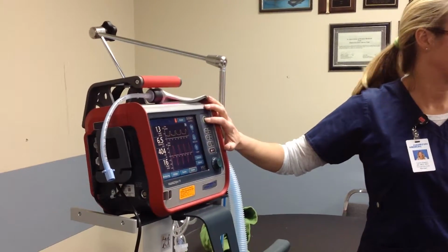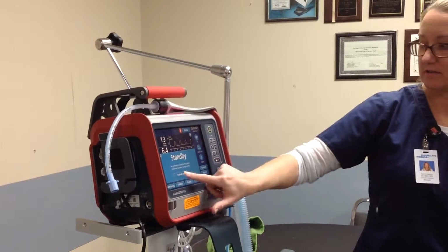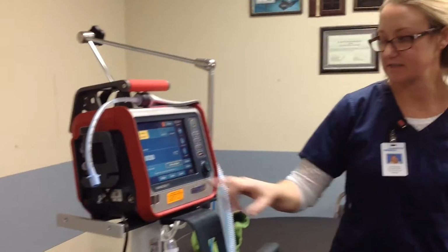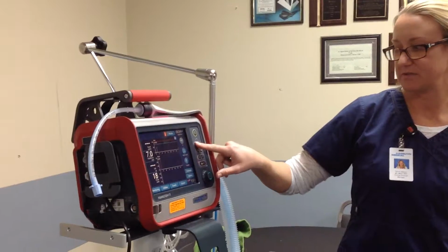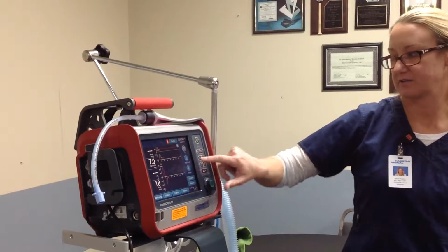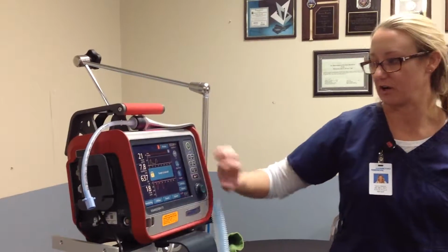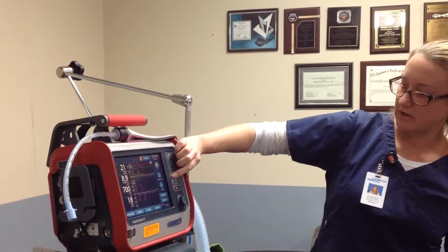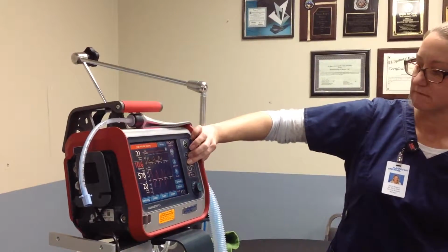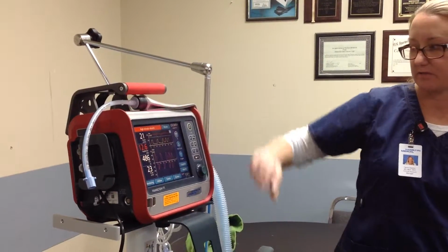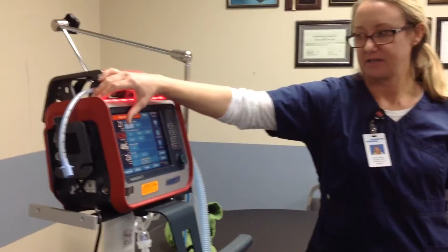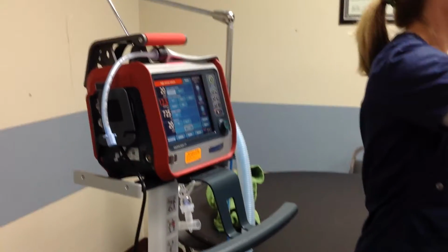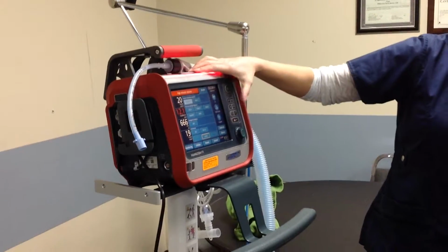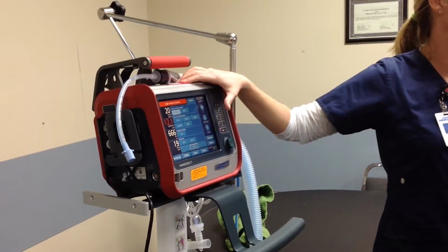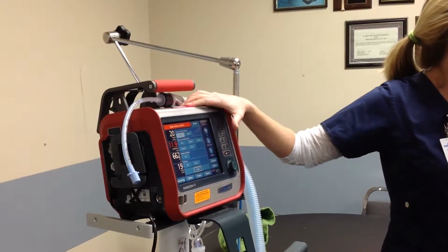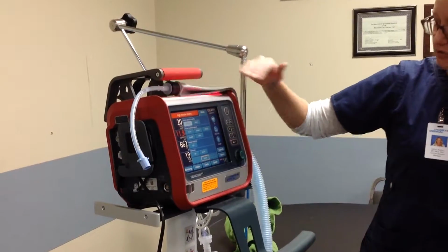This is also your start standby screen. So if I push this, it's a two-step process to activate standby. This dims the screen. This locks the screen so that you can't inadvertently make changes. This lung button gives you manual breaths. This is one way that if you were using SIMV Plus and you wanted them to get up to their volume faster, you could hit this repeatedly, and by doing this, really what you're doing is increasing their minute ventilation, so you could get them to ramp up to the volume that you're targeting quicker.